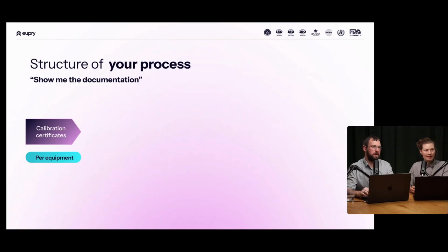So the question we see asked a lot: show me the documentation, show me the calibration certificate for this. Because it's all well to know your process, understand it, and show confidence that you understand exactly what's going on. But if you can't prove that these rationales are backed up by calibration certificates, for example, it's not going to be of value to an auditor. So auditors like myself love to see objective evidence that actually backs up what you're showing in your SOPs, for example.